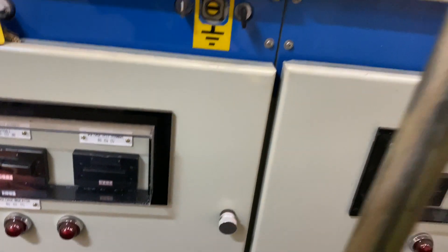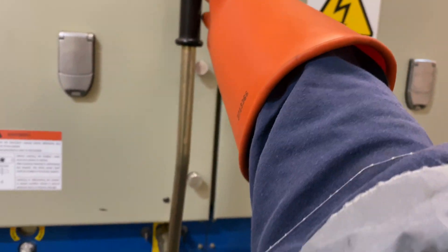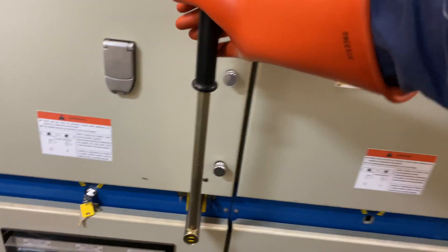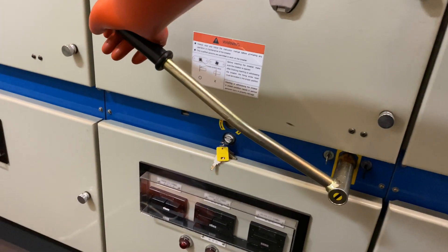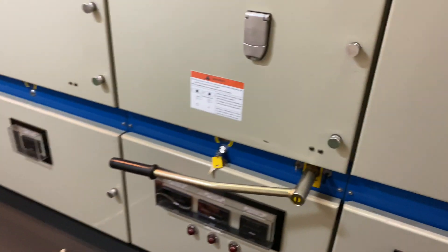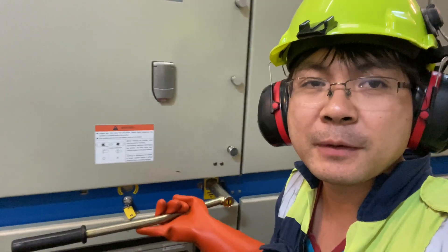Now after we put the excitation key, we can put this handle for grounding so that we can earth the system. You can see this marking here — this one needs to go counterclockwise. So now the system is earthed and we can remove this.